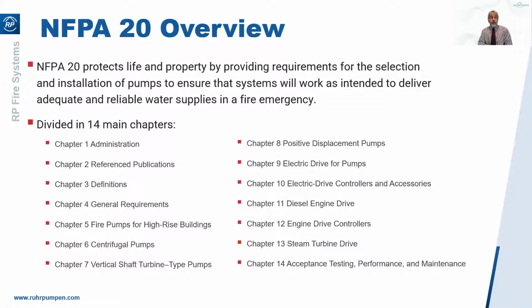So NFPA-20 covers all aspects of a fire pump installation, not just the centrifugal pumps, vertical pumps, positive displacement pumps, but also the controllers, electric drivers, diesel engine drivers, even steam turbine drivers. I've never sold a fire pump driven by a steam turbine, but I'm told there are some out there somewhere. Also testing, performance, maintenance. So it's the full thing.